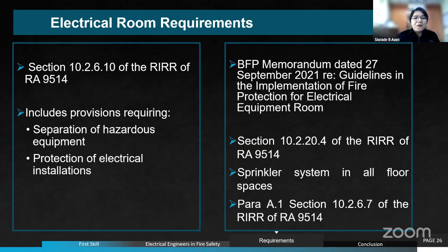Especially for high-rise buildings, according to para A.1, Section 10.2.20.4 of the IRR of RA 9514, a sprinkler system is required in all floor spaces, including our electrical room, generator area, and mechanical areas—we need to provide a sprinkler system. However, to guide us on whether we can avoid installing a sprinkler system in our electrical rooms, we have the provision of para A.1, Section 10.2.6.7 of the IRR of RA 9514, which states that the installation of our sprinkler system should be in accordance with NFPA 13. So we have that reference from the Fire Code.